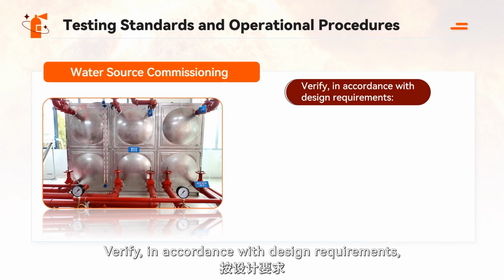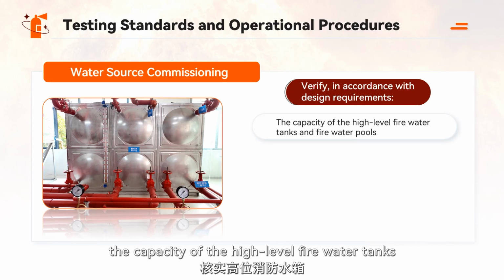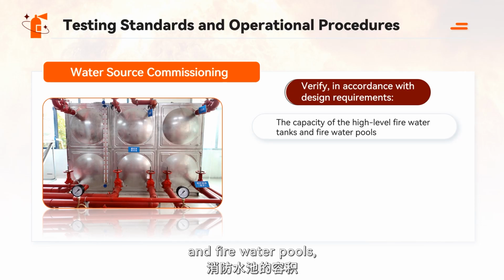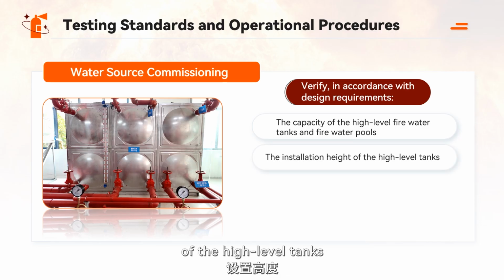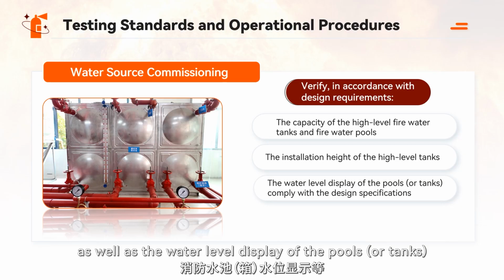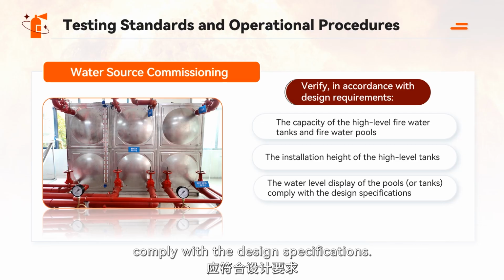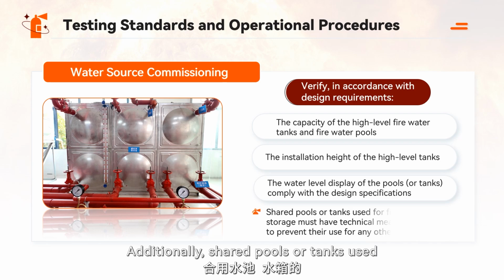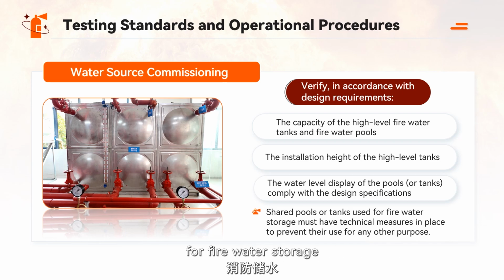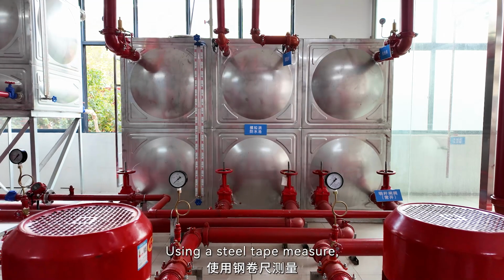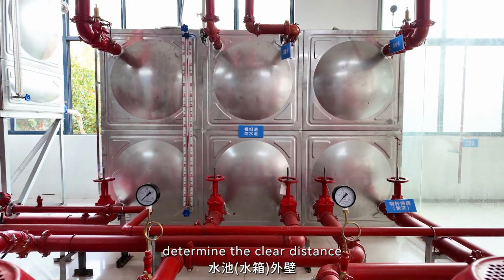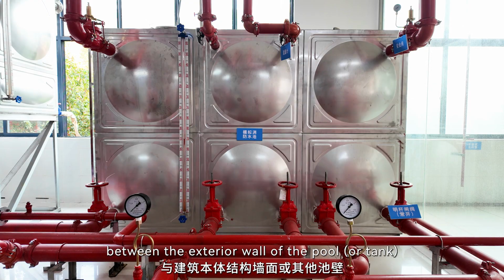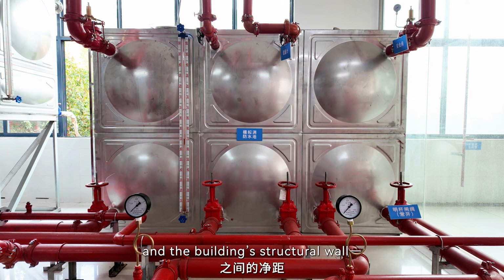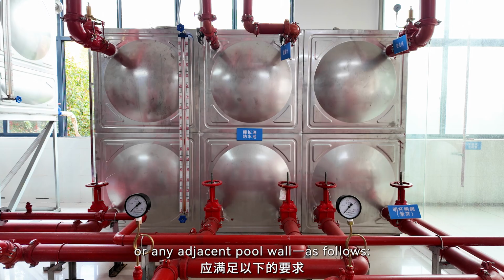1. Water source commissioning. Verify, in accordance with design requirements, the capacity of the high-level fire water tanks and fire water pools, and ensure that the installation height of the high-level tanks as well as the water level display of the pools, or tanks, comply with the design specifications. Additionally, shared pools or tanks used for fire water storage must have technical measures in place to prevent their use for any other purpose. Using a steel tape measure, determine the clear distance between the exterior wall of the pool, or tank, and the building structural wall, or any adjacent pool wall, as follows.